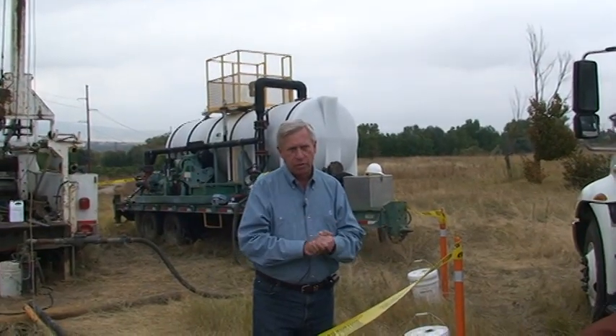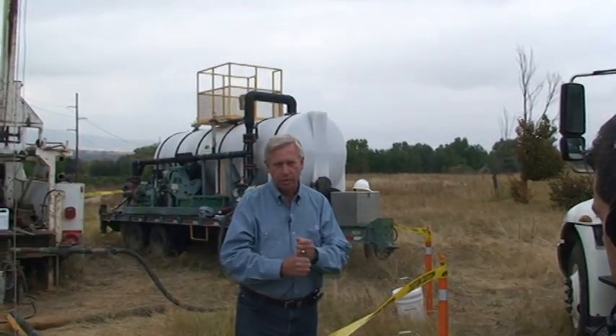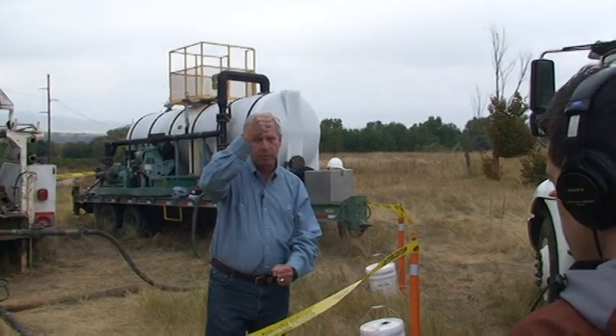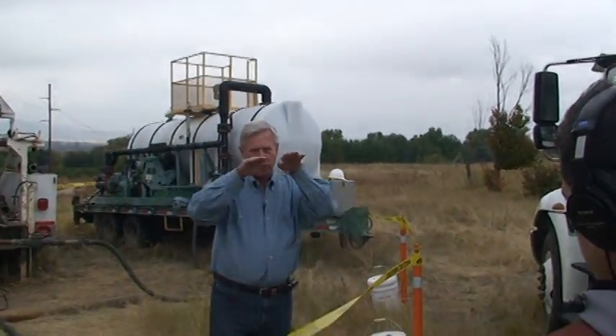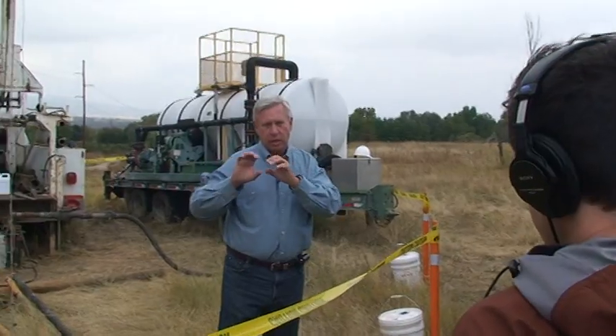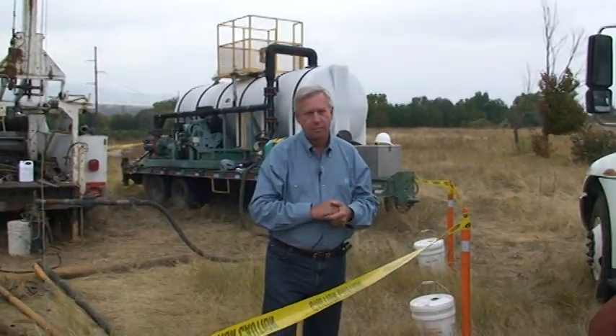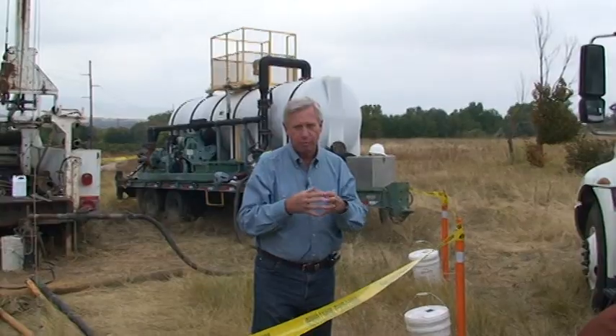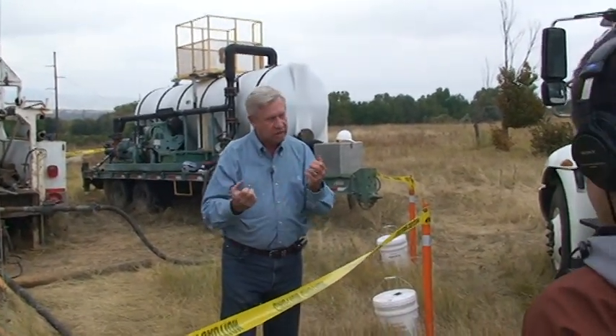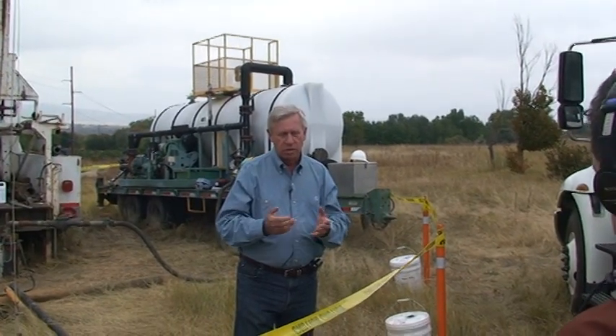And then there's a cap, of course, and the well has inside it, when it's completed, a pump and motor unit. It has the electrical wire going down and the drop pipe coming up. So it's a submersible pump and motor. And on the top of the well is a cap. You don't even see the discharge. The discharge goes out through the ground through a unit called a pitless adapter. The discharge, a pipe, goes to the supply. So we're replacing the pump, the motor, the wire, and the drop pipe that were all contaminated and old. And so everything will be new inside the well once it's completed.